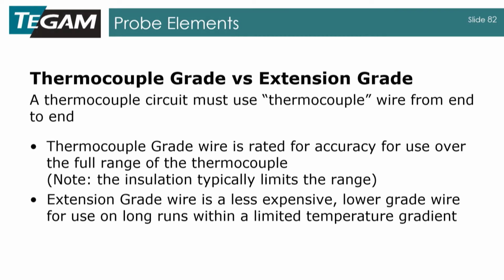Extension grade wire is going to be a little less expensive, but you can use lower grade wire if you know that you're using a lower temperature gradient. So basically, let's say you're using type K and you need to measure 2,000 degrees F in type K. You're going to want to use a thermocouple grade wire because you're over on the extreme of K. Now, let's say you're using type K, but you're just measuring an oven at 300 or 400 degrees. Well, because you're not using the full span of K, you can use a cheaper extension grade wire to get to that measurement because you know you're not going outside the limits of that thermocouple span.